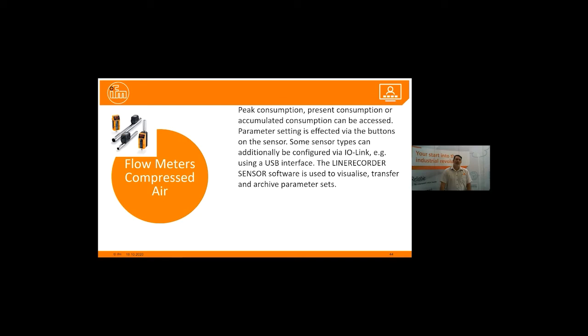Peak consumption, present consumption or accumulated consumption can be accessed. Parameter settings are effected via the buttons on the sensor. So you parameterize it with the local buttons on the unit. Some sensor types can additionally be configured via IO-Link using this LR device software.